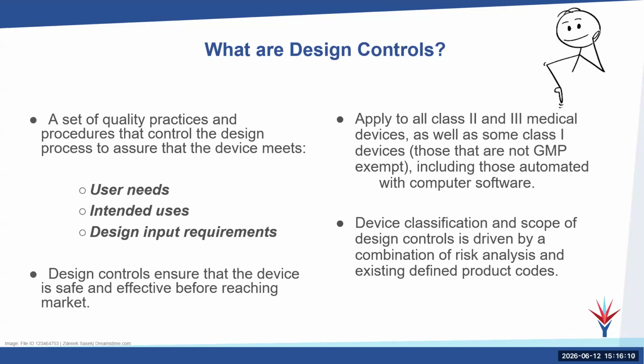And all of that rolls into the risk assessment that you do from the start of the product design all the way through. That's a living document that, if you are controlling your design efficiently, you're looking at frequently, at the risks that are upcoming or have been overcome, to see what the impact has been on the design input requirements, meeting the user needs, and defining the intended use. It applies to all Class 2, 3 medical devices, as well as some Class 1 devices and in vitro diagnostics. It also includes those automated with computer software.